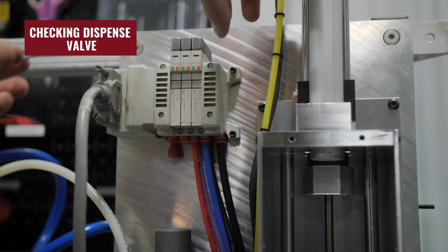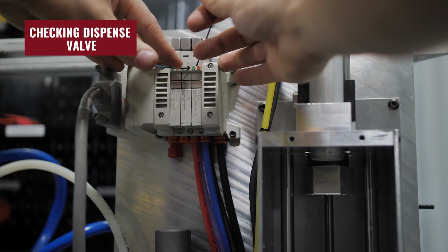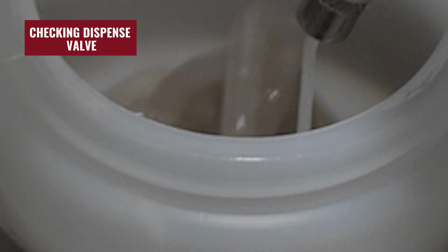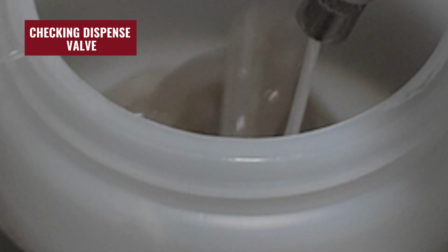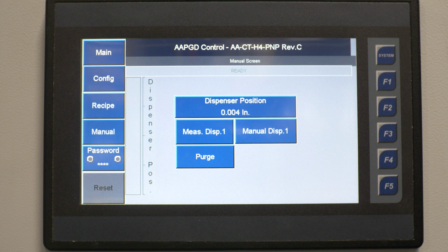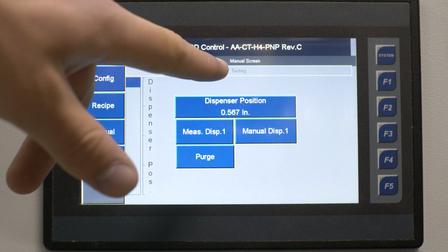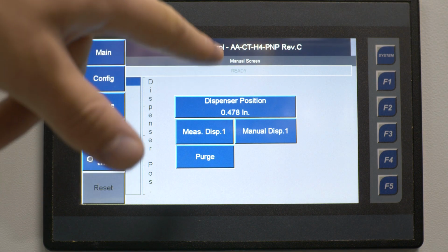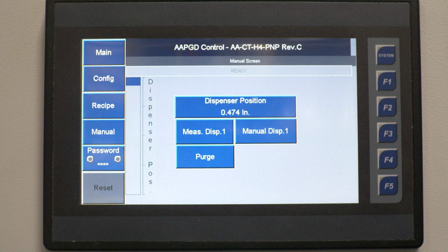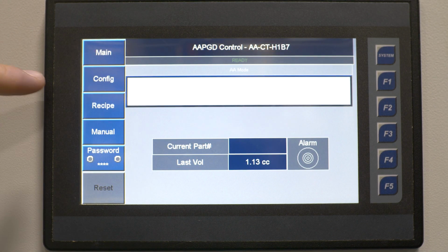Now we will test the dispense valve. So we will hold the fill valve on and pulse the dispense valve. And as you can see, the material is coming out while I'm pushing the dispense button. The way it does a compression test is when it refills the chamber, it automatically does the compression test before wanting to dispense again. It's right at the end of here. It says testing. Now it's ready. If it fails the compression test, it should fault out, and you'll be able to see that on the main screen.